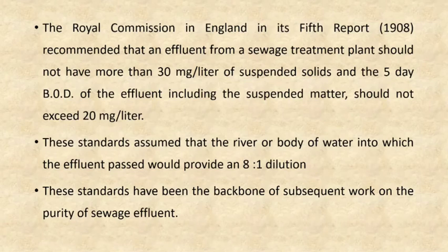So there should be suspended solids less than 30 mg per liter and the oxygen demand should not exceed 20 mg per liter. The standard which is used is 8:1 dilution, which means 8 parts is the river or body of water and 1 part is effluent. So 8:1 dilution, and this is the standard which is used nowadays also.